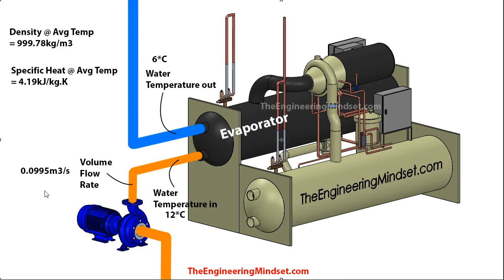For the metric calculation, we're going to assume that this pump is providing water at 0.0995 meters cubed per second, and that the return water coming from the building — from the AHUs, fan coil units, etc. — is entering the evaporator at 12 degrees Celsius and leaving at 6 degrees Celsius. The density of the water at the average temperature of 9°C is 999.78 kilograms per meter cubed, and the specific heat capacity is 4.19 kilojoules per kilogram per Kelvin.